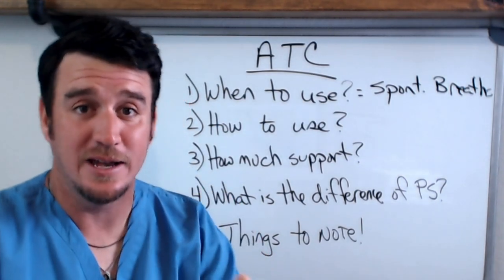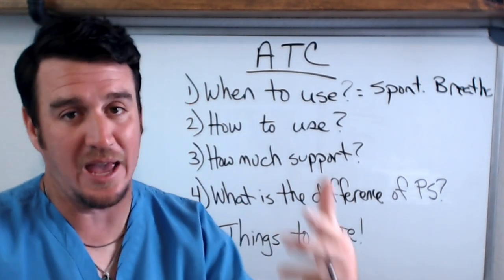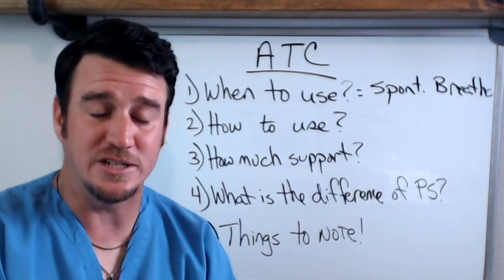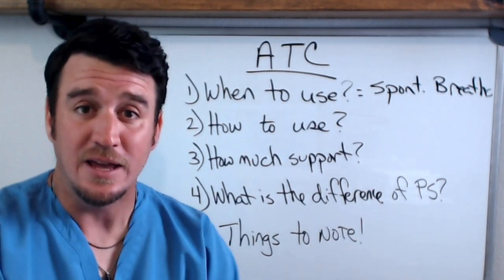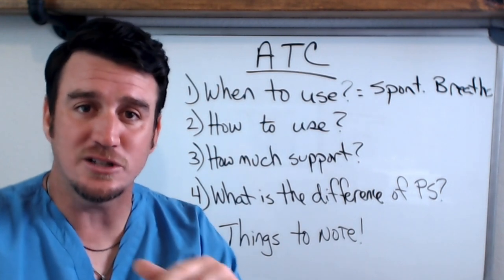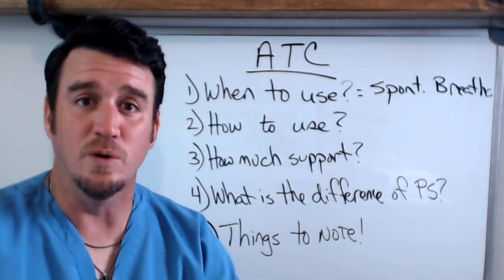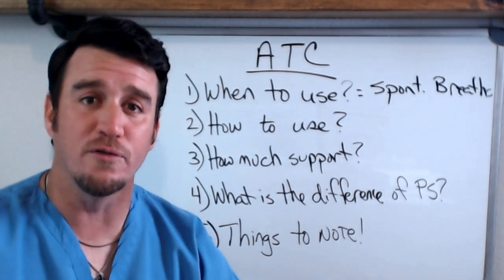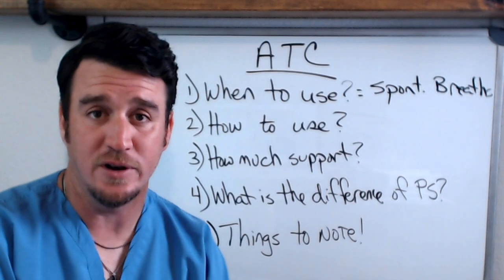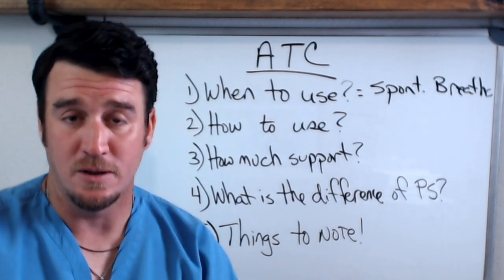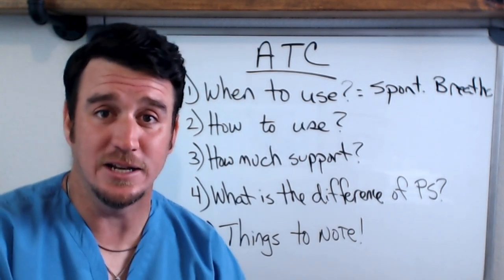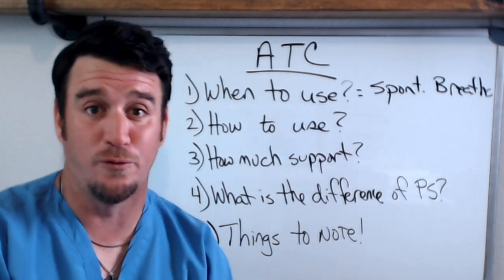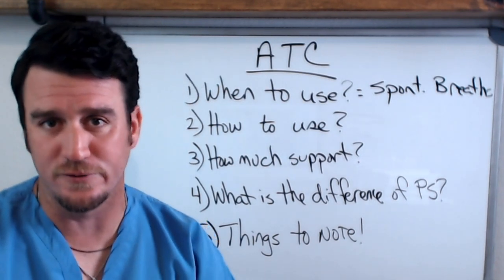This could be SIMV, this could be CPAP, this could be APRV or bi-level — any type of mode where a patient can take a spontaneous breath. ATC, automatic tube compensation, will be relevant to providing enough support to that patient to overcome the resistance of the artificial airway. That's what ATC does: it compensates for the resistance of the artificial airway.